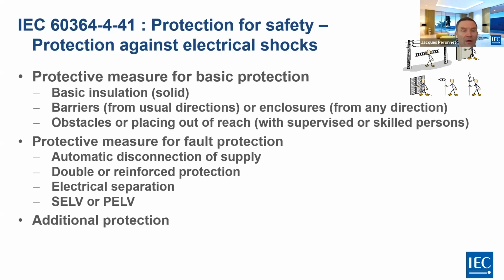We then describe the protective measure for fault protection. So it could be done by automatic disconnection of the supply, or it could be done by double or reinforced protection, electrical separation, and safety extra low voltage or protective extra low voltage. And then the last measure that we could apply is what we call additional protection, to have a protection which is given in addition to basic and fault protection.